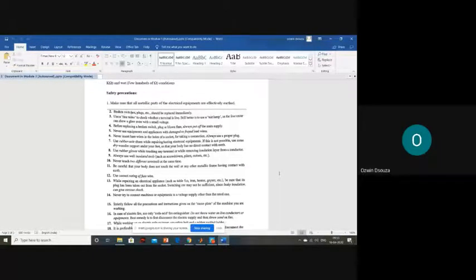Now point number 6. Normally people call this a jugaad kind of arrangement. If you don't find a plug point, what do you do? You just use your mouth to open up the wires, and then start inserting the phase and neutral wires directly into the socket points. That is actually very dangerous, because while inserting, if the phase and neutral wires accidentally come in contact, you will create a dead short circuit. So in an attempt to make a jugaad, you will end up spoiling your entire wiring system.